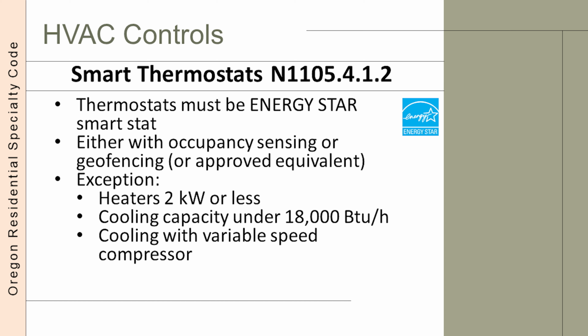The list of Energy Star thermostats that meet these requirements has increased significantly between the time the code was written and the time of this recording. One additional note is that there is no requirement to have Wi-Fi to the home. There are some exceptions for not requiring an Energy Star thermostat. Any heater of 2 kilowatts or less, which would cover nearly every wall heater or baseboard heater used in a typical home. Any cooling unit with less than 18,000 BTUs per hour or 1.5 tons of indoor capacity.